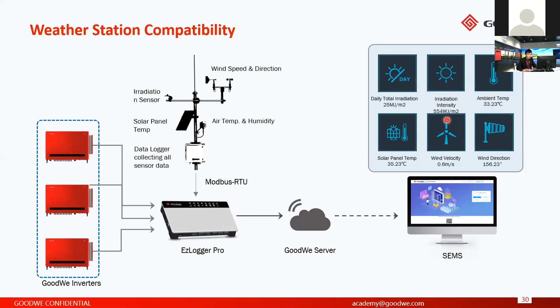And here's the weather station. The weather station can be connected to our data logger. Okay, it can't connect to the inverter directly, but it can be connected to our data logger. And our data logger uses the Modbus RTU protocol. So if your weather station already has this protocol, your weather station can communicate with our data logger directly. So just make sure your weather station has Modbus RTU protocol. Then your weather station can communicate with our EzLogger Pro directly. And the weather station data can be shown in our SEMS portal. Like here, we have the solar panel temperature, wind speed, wind direction, irradiation, and ambient temperature.